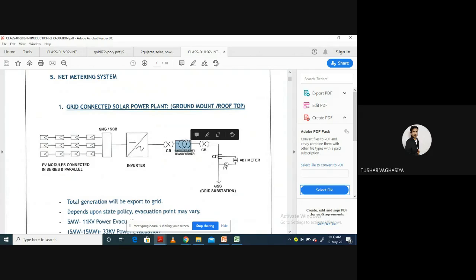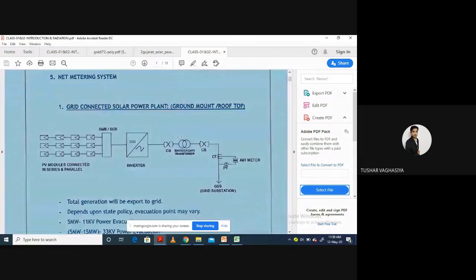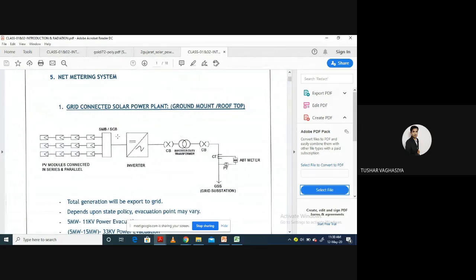The sizing of the inverter duty transformer depends on the type of solar power plant and its size also. If you want to design the inverter duty transformer, we have to give the data of the inverter side as well as the grid substation side, so the designer can design it by comparison and match the frequency of both. So we are using an inverter duty transformer in the grid connected solar power plant, and before the inverter duty transformer, we are putting a circuit breaker for protection.